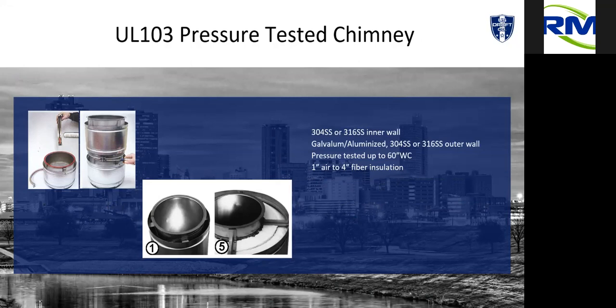Okay, so it is a different temperature rating, but it can be made of, again, 316, 304, aluminum, galvanized outer jackets, all kinds of different things. It's also pressure tested to a higher rating because your power burners can have higher pressures. Now, it says up here, pressure tested to 60 inches.